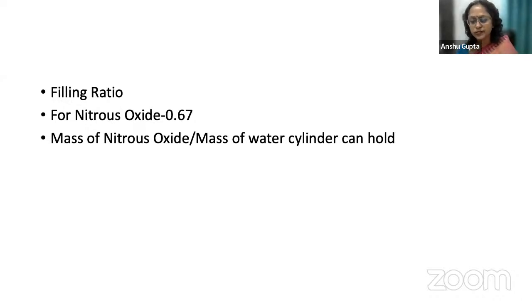So how do you know how much gas is in the cylinder? That is by the weight of the cylinder. So this is the filling ratio, the mass of the gas in the cylinder as compared to the amount of water that cylinder will hold. That is 0.67 for nitrous oxide.